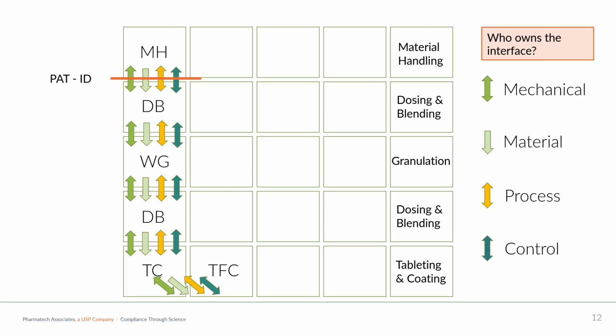Because usually you'll see that PAT instrumentation—whether material identification, blend uniformity, loss on drying, particle size, you name it—is usually positioned in these intermediate sections, these interface sections. Not only because it's a logical position, but also because you may have sampling points and diverter points there.